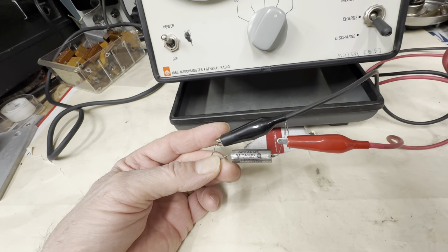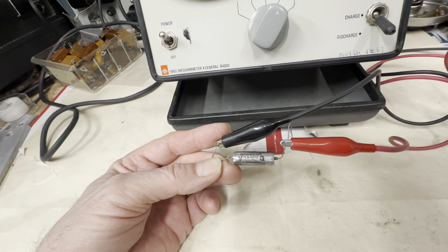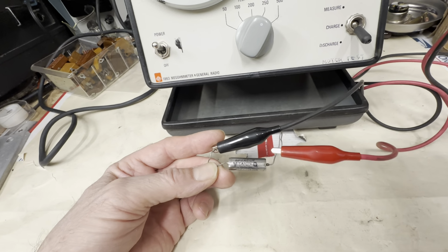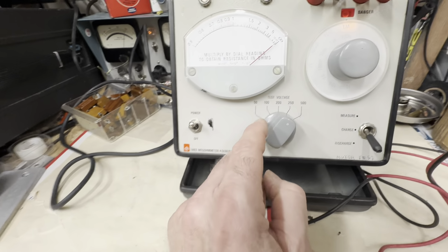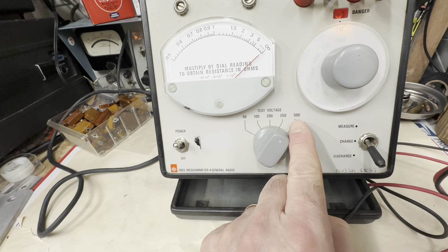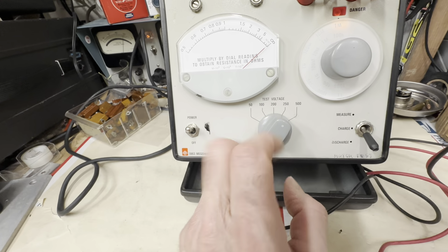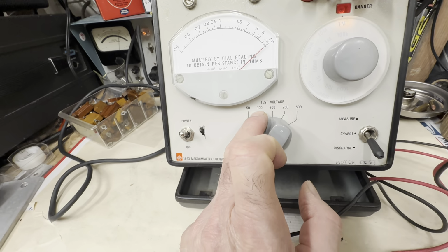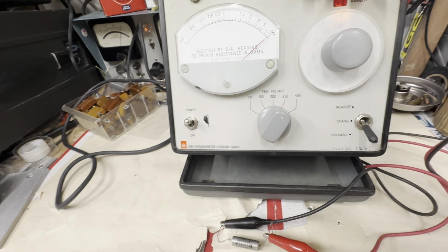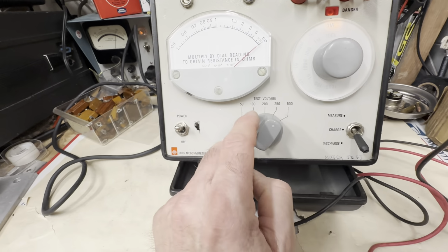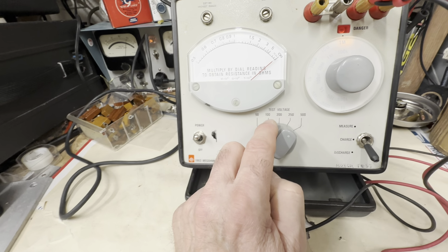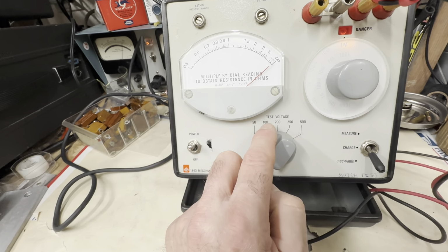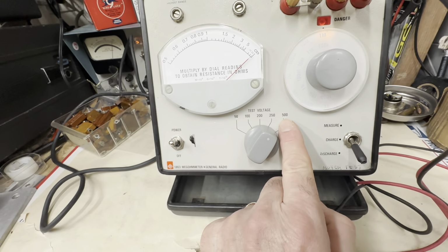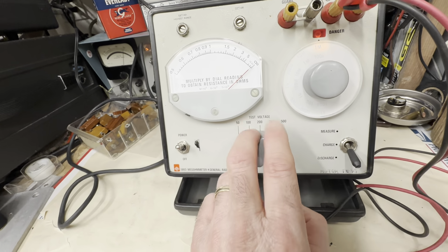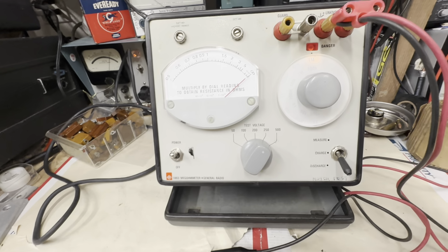We're anywhere from 70 to 60 years later, and a lot of these are still good. Let's check this one for leakage. Okay, since this is a 400 volt cap, we can't go 500 volts on it, but we can go 250. That's the neat thing about the 1863 here, you can go 50, 100, 200, 250, and 500 volts. Standard resistor testing and component testing is typically done at 100 volts, and insulation tests done at 500. So this supplies both voltages that you need for industrially testing something, which is cool.